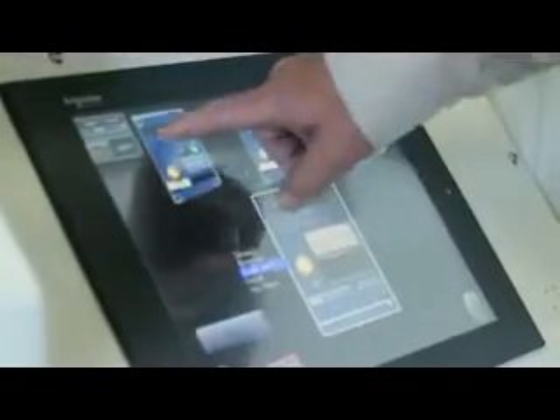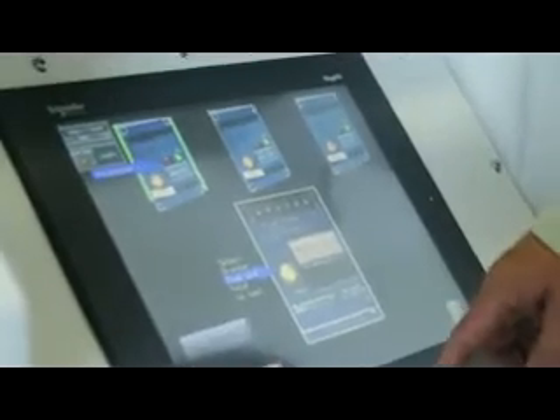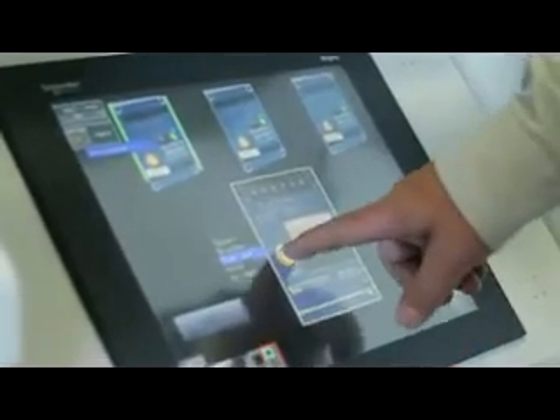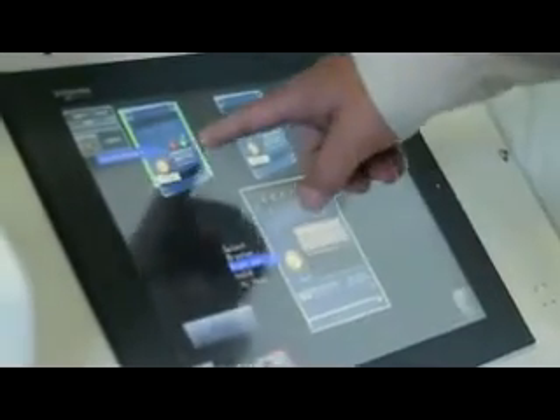So again, if we go back to home and we want to do something on a ground fault, in order to test the ground fault, we can select which unit we want to do a test on. I know the top one is closed at the moment, so now if I hit push to test, you notice that the ground fault relay now indicates that it's open.